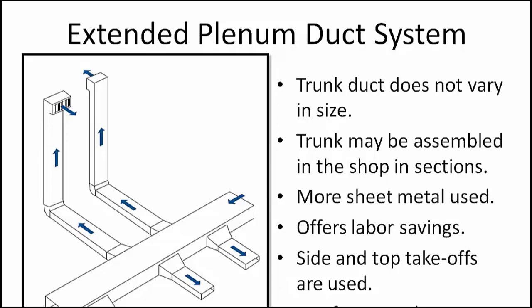The main feature of the extended plenum duct design shown here is that the trunk duct does not vary in size even after the branches have been taken off — it remains constant in cross-sectional area. For example, if an 18 by 8 inch trunk duct is connected to the supply plenum, the size remains the same throughout the length of the duct. From the standpoint of duct fabrication, this has great advantage. The entire trunk can be constructed at a shop in sections; careful measurements of varied shapes of trunk ducts are not needed. Branch duct locations can be marked on the trunk after the duct has been installed, and the takeoff connections installed on the site. The shape of the branch takeoff connections can be standardized. Obviously, more sheet metal is used in this arrangement than in a trunk duct with reduced sections, but the savings in labor more than compensate for the cost of the additional sheet metal.